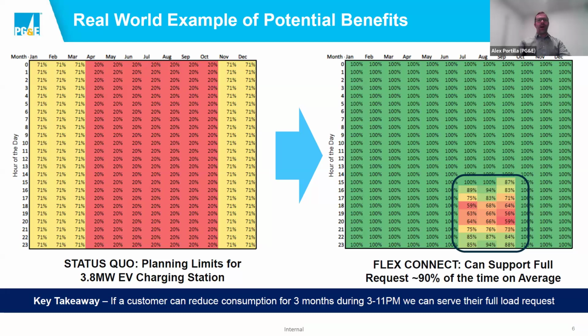On the left, you have our standard review process, the industry standard planning process where you look at the worst case scenarios, because we plan the grid to meet all scenarios. This site was given a load limit, so they were allowed to connect 20%, or 700 kilowatts, of that 3.8 megawatts in summer, and up to 2.2 megawatts in winter.